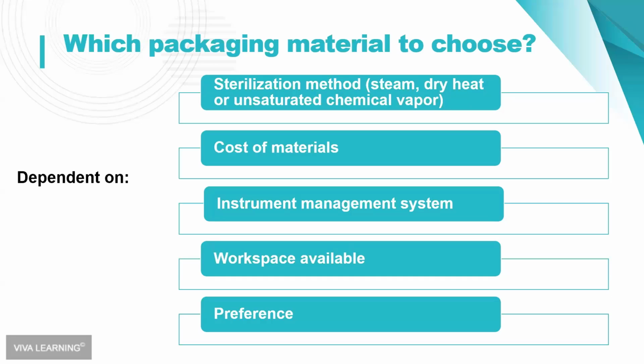And this may already be predetermined in your practice, but if you're looking to make a change or you're not sure if what you're doing is appropriate, these are the things that typically go into that decision-making process. What kind of sterilization method are you using? Are you using a steam autoclave? Are you using dry heat or unsaturated chemical vapor, a chemclave? And each of those types of sterilization methods may have packaging materials that are appropriate for or not appropriate for that.